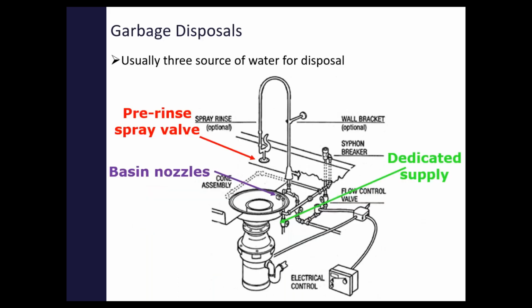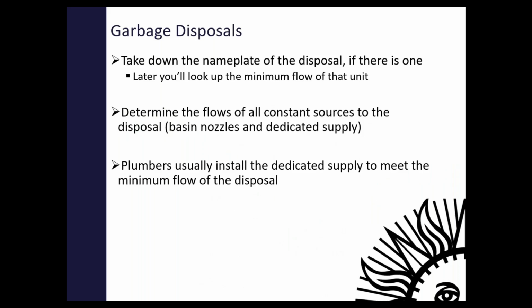Garbage disposals. So the important thing to look for here is there is a constant flow required by your garbage disposal. Usually, the ones I've seen have been between 5 and 9 GPM. So to make up that 5 to 9 GPM, you have a combination of basin nozzles and a dedicated supply that goes directly into where the garbage disposal blades are. What you want to check here is, does the sum of the basin nozzles and the dedicated supply equal just the bare minimum of what that garbage disposal requires? Most times you'll have a plumber come in and they'll just install a dedicated supply of a half-inch pipe. Well, a half-inch pipe gives you a lot more flow than 9 GPM plus the basin nozzles.